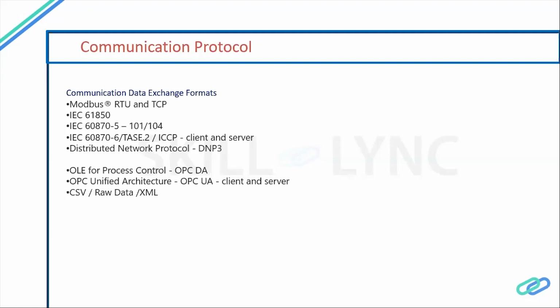The secondary server stores the data. If the primary server comes up again, the primary server automatically takes the data from the secondary server also. So this type of communication protocol is there. OPC-DA I've already explained, and OPC, so CSV or raw data XML. CSV is basically for every 15-minute data you push to a CSV or XML file. So for a third-party device, non-critical data is taken from a CSV or XML file and displayed on your dashboard. Basically, this type of communication is required for top management purposes, because top management don't want data for every 1 minute. They want 15 minutes, or 20 or 30 minutes, or 1 hour only. So what is the generation? What is the plant performance? We are using CSV or raw data XML for these things only.